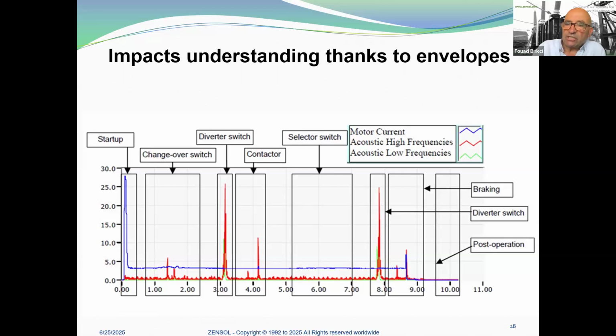The sequence of operations associated with an OLTC is described in the operation guide provided by the OLTC manufacturer. Most of the time, this guide describes the operation of every single mechanism element acting during the switching operation, such as the diverter, the selector, auxiliary contacts, main contacts, and so on. With this information, the relation between impacts and mechanical parts can be easily identified on the footprints, as shown in this picture.